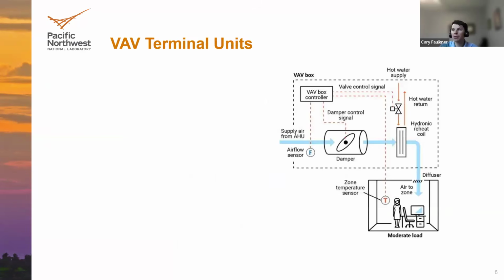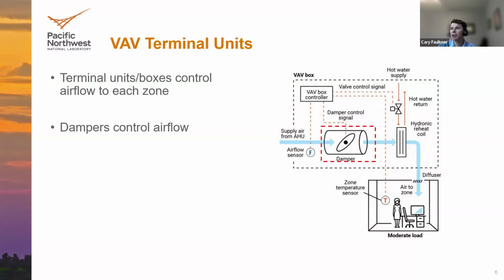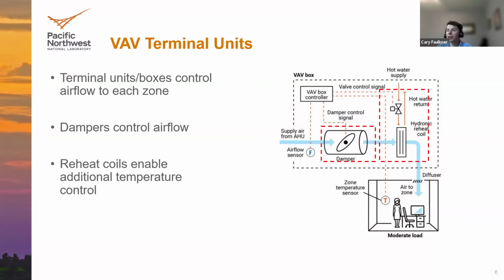So now let's talk about those VAV terminal units, also known as VAV boxes. These are a critical part of the VAV system because at each of the zones, which could be an individual room or maybe a group of rooms, a group of office spaces, you have these boxes that have two key aspects, I'd say. Controlling the airflow using these dampers, based on how much ventilation or heating and cooling is needed at the zones, and then reheat coils, which enable additional temperature control. I'll talk about this a little bit more, but there's a feedback loop between what's happening at the air handling unit and these dampers, where the dampers open and close, and that tells the air handling unit something about how much airflow is needed for these zones.